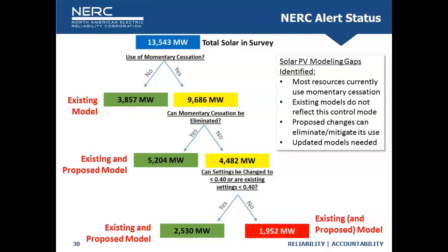One of the big findings from the modeling perspective was that the vast majority of resources use momentary cessation, but the models used in the interconnection-wide base cases do not accurately represent that control mode. So 9.6 gigawatts of 13.5 gigawatts are using momentary cessation, and very, very little of those are accurately representing it in the models. That identified an existing modeling issue that needs to be addressed.